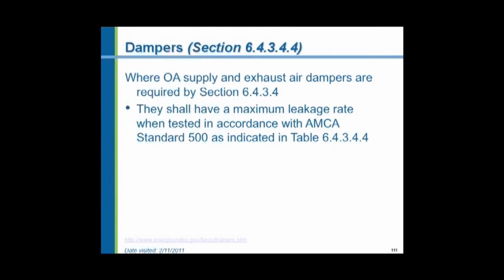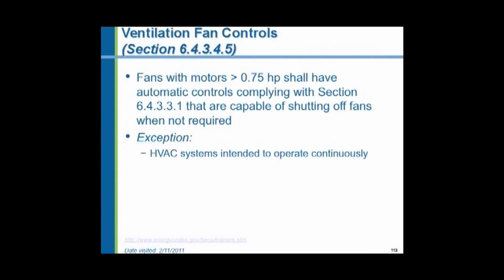Now, where outside air and supply and exhaust air dampers in the building ventilation systems are required, again, they have these leakage rates, and they're certified in accordance with the Air Movement and Control Association Standard 500. Ventilation fans larger than 3/4 horsepower shall have automatic controls capable of shutting off the fans when they're not necessary. So not only the heating and air conditioning systems, but any other fans operating along with it. And the only exception is if they're intended to operate continuously for some unusual reason.